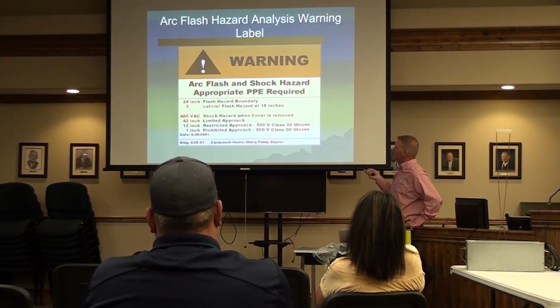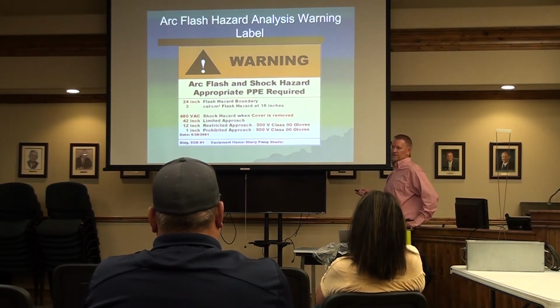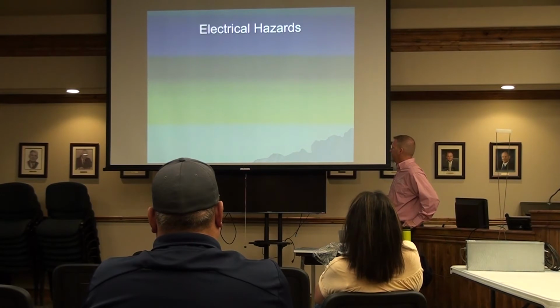This is the arc flash analysis that has been done. So 24-inch flash hazard boundary, 3-calorie flash hazard at 18 inches, and then all of the details, the date that it was done, the building, and what this is, the equipment name. And then if there's anything changed, transformers, anything that changes this value, it has to be reevaluated, obviously, because now it could be higher, could be lower, we don't know. So that's basically what the arc flash analysis would provide.